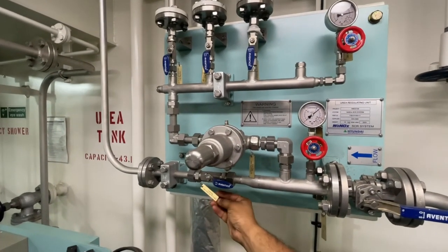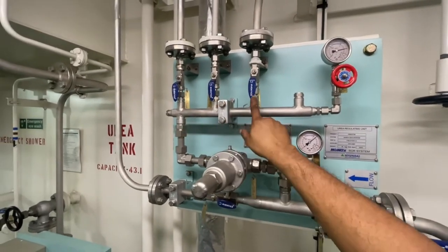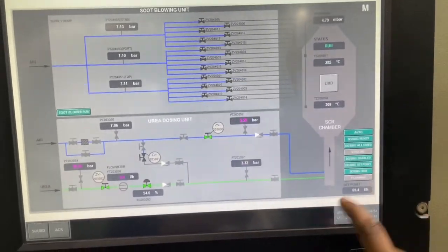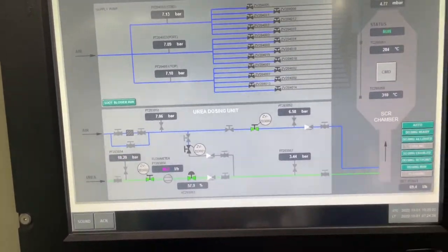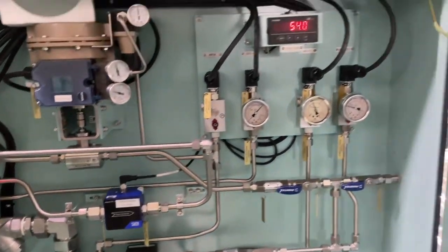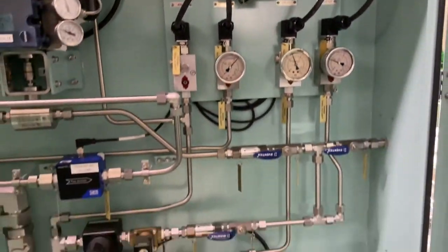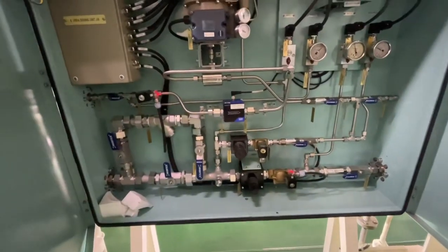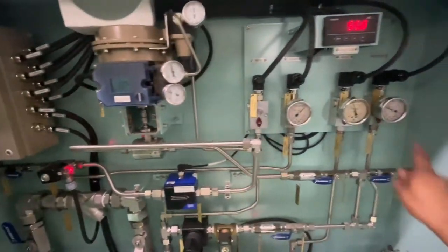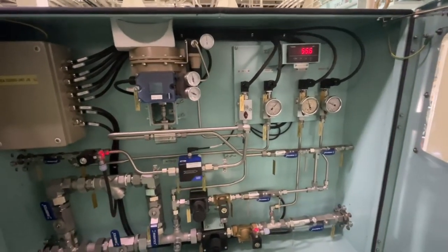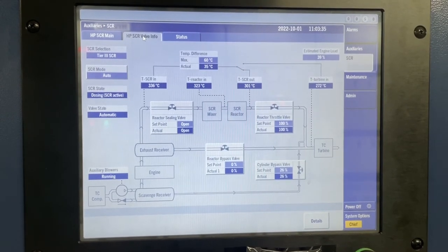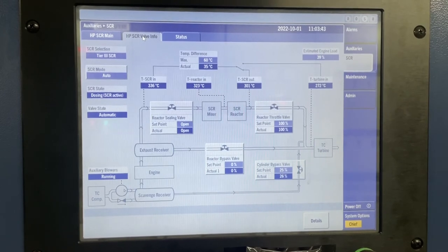The urea outlet has four outlets: one is for the main engine and another three are for auxiliary engines. The urea will dose to the mixing chamber by vaporizer with the help of assist air, after passing through the flow meter. This is how the assist air goes to the urea nozzle. From the urea pump, urea comes through the flow meter and goes to the urea nozzle. Once the urea starts to flow, the SCR state will change to dosing SCR active from dosing enabling.